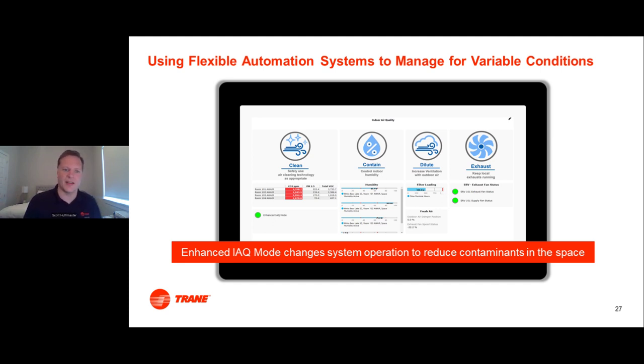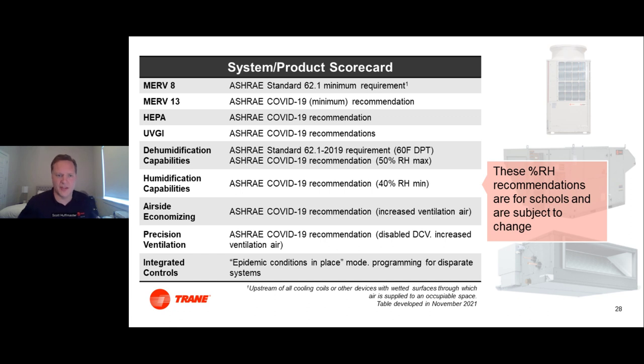So if you see in the bottom left of that little picture there, you'll see a little green button says enhanced IAQ mode. That means the ability to toggle our system into an epidemic conditions in place, bringing in as much outside air as possible, running your systems longer, again, prioritizing the health of a space as opposed to the energy efficiency. This is something we're seeing sensors allowing us to do. Now with that, I'm kind of touching on something that I think many of you on this call recognize. IAQ and a focus on IAQ and even IEQ is leading to a new look at how we design the systems themselves. On the left here, you'll see common things that we're seeing as parts of how we deliver on IAQ in a building.